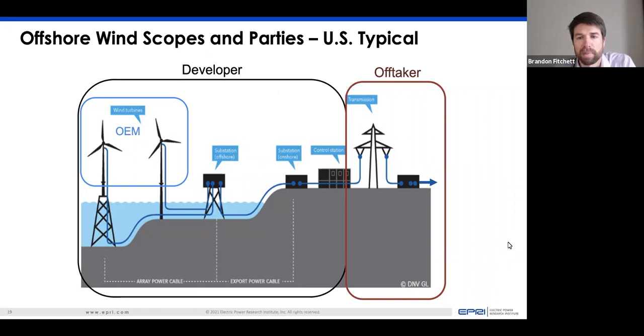So we're going to look at a couple plant setups. And again, we just zoomed in on the wind turbine for a second. That's really in this OEM scope circled here, which fits in the developer box. The developer typically selects an OEM, lays out the plant, and is responsible for the array or the collection system. And here in the US, a lot of times, and this follows the same model as onshore wind, the developer is starting to be responsible for the run to shore, the transmission to shore, and all the way into the nearest point of interconnect to the utility or offtaker.